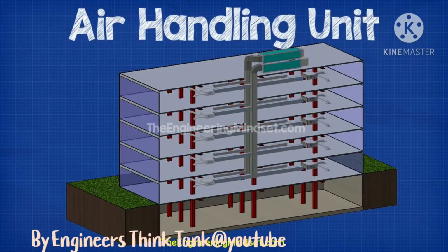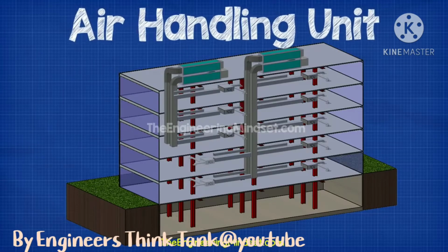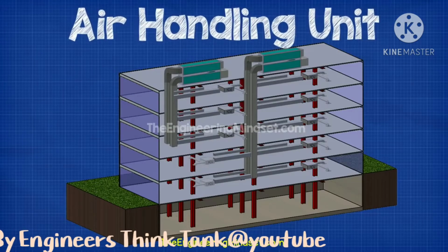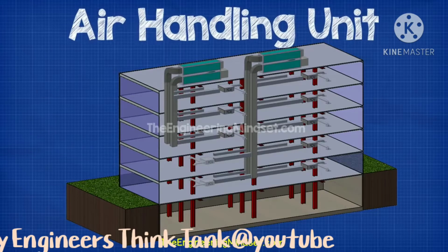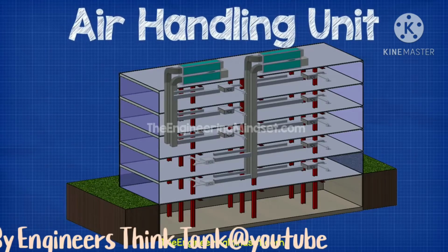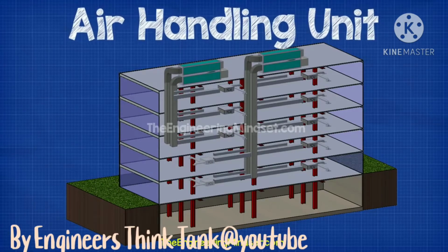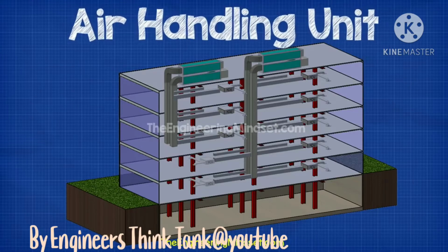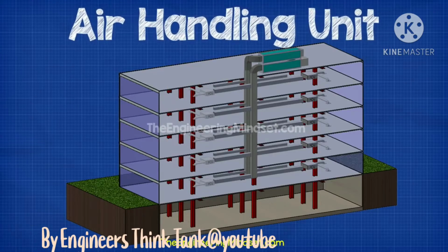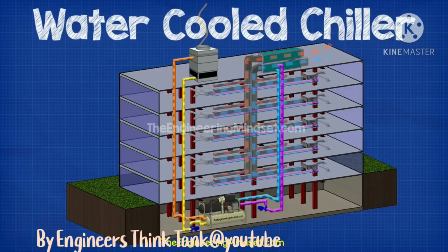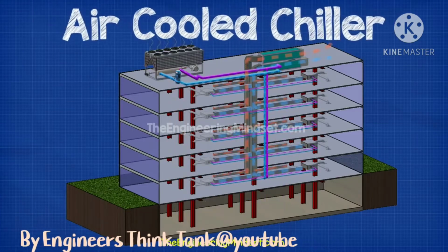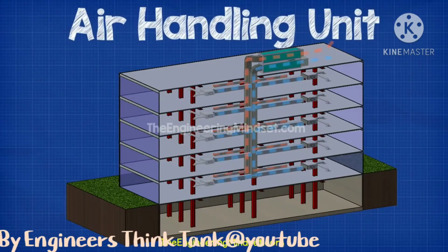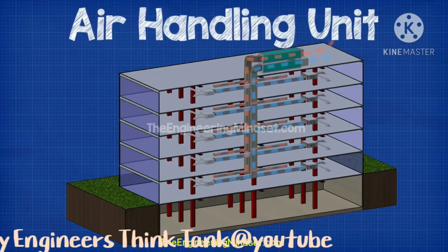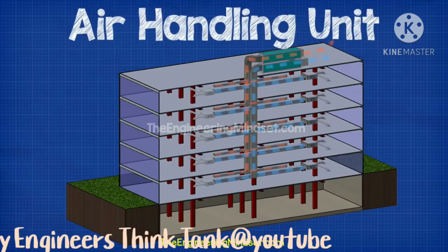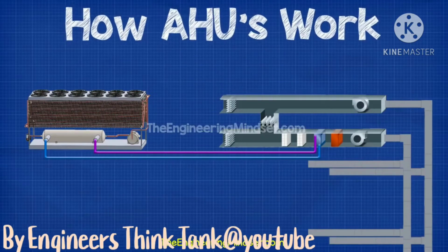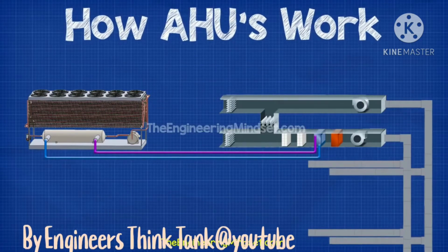Sometimes one AHU will supply the whole building, but it's common in newer buildings to have multiple smaller AHUs feeding different parts to provide a better indoor environment, as well as resulting in energy savings. AHUs typically do not have their own cooling system built in. Instead, they will be connected to a central plant, water or air-cooled chiller. Occasionally, they will use some sort of split AC unit, and you can also find these connected to district cooling networks. AHUs are connected to ductwork, which provides a defined route for the air to travel around the building.